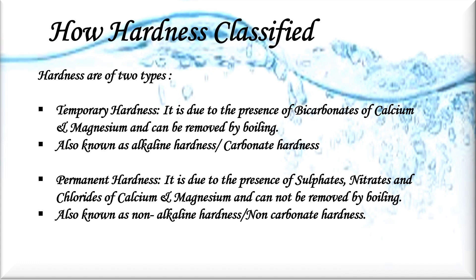Hardness is classified into two types. Number one: temporary hardness, which is due to the presence of bicarbonates of calcium and magnesium, and can be removed by boiling. It is also known as alkaline hardness or carbonate hardness. Number two: permanent hardness, which is due to the presence of sulfates, nitrates, and chlorides of calcium and magnesium, and cannot be removed by boiling. It is also known as non-alkaline hardness or non-carbonate hardness.